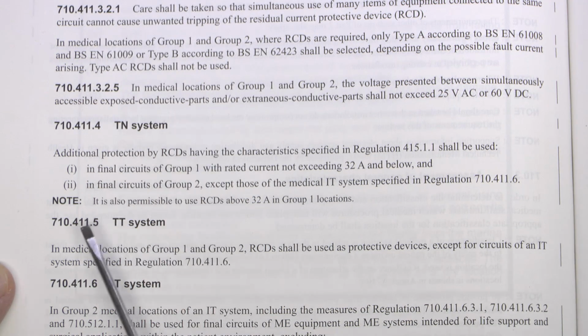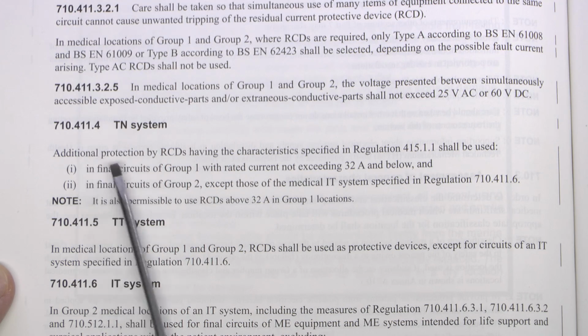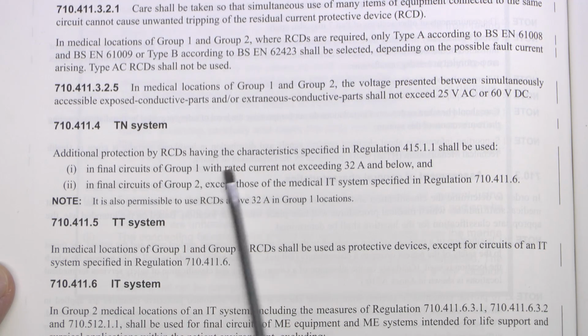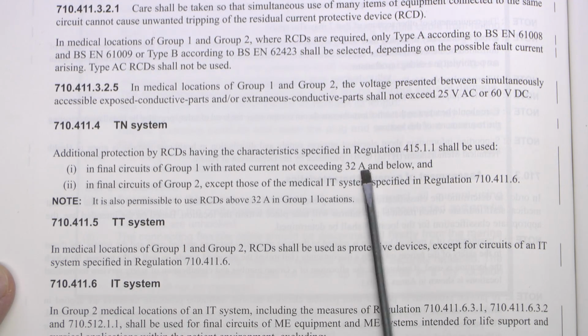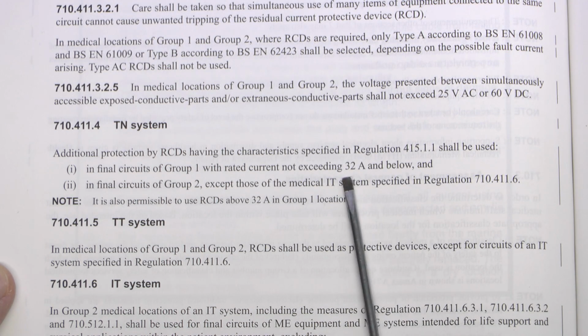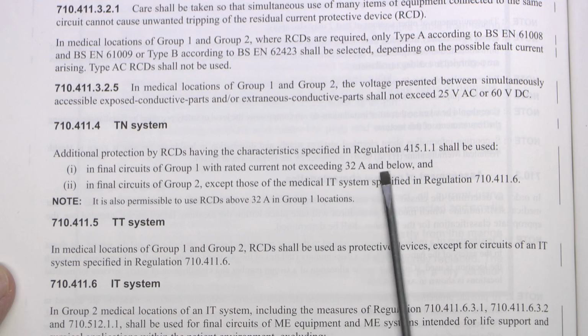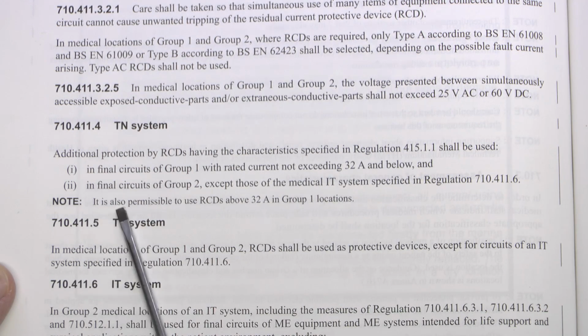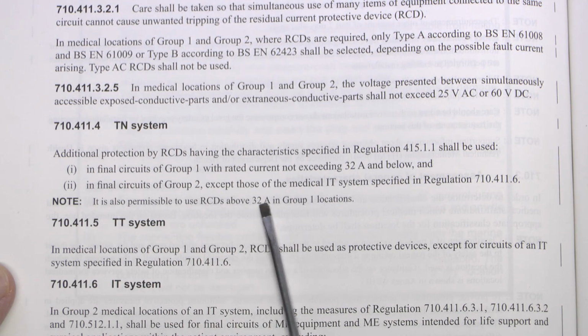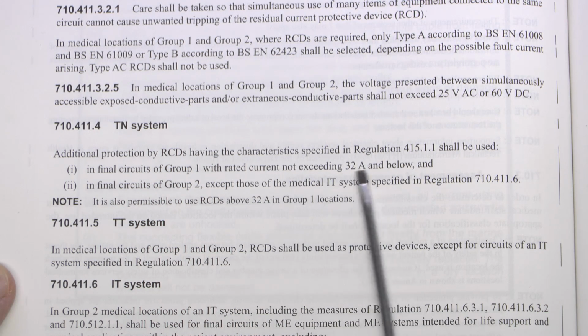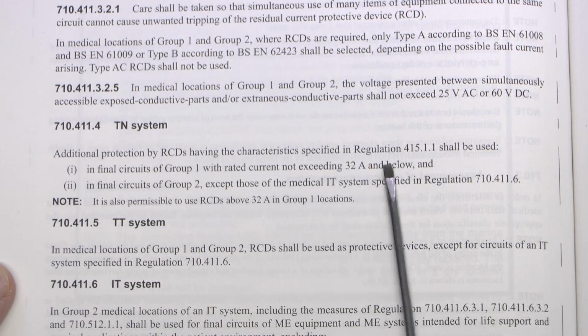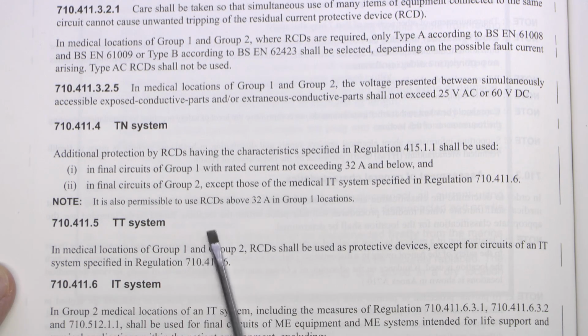Now 710.411.4 has been changed as we've got the additional protection thing being added in here, and that's how it was in the previous part. And the main change here is that we've got in final circuit of group 1, with rated current not exceeding 32 amps and below. Previously this was 63 amps, so that has basically been cut in half there. And there's also a new note which says it's also permissible to use RCDs above 32 amps in group 1 locations. So rather than being required up to 63 now, it's basically up to 32, and you can still use them above that if desired.